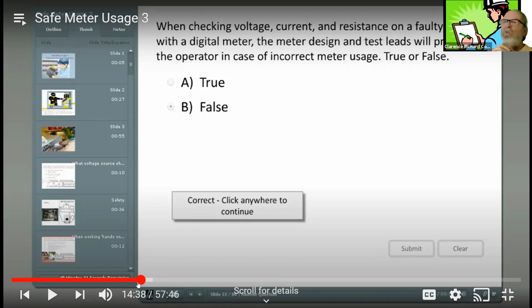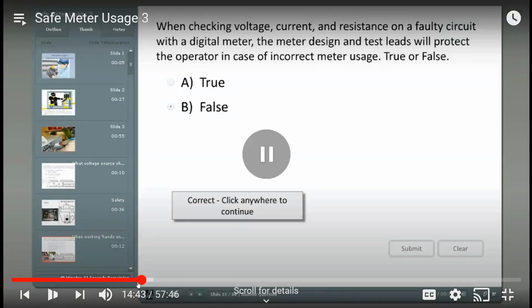I would be entirely dependent on that. They're saying if you use it wrong, that's false. Good meter, but you're reading the wrong spot. You're not protected. True. Thank you, David. Okay, thanks. Design and proper test leads are no substitute for incorrect meter usage.